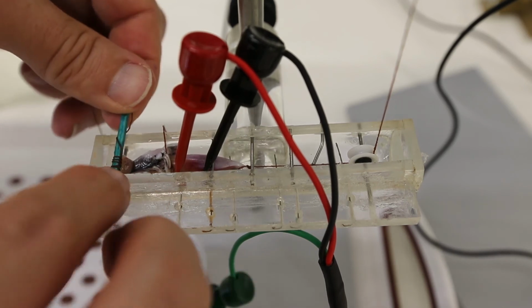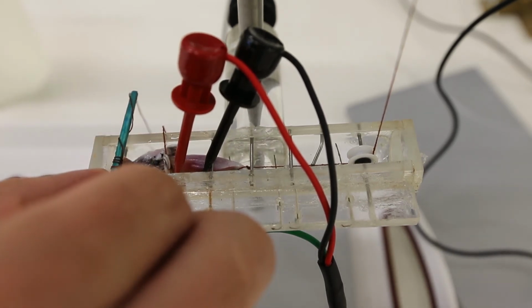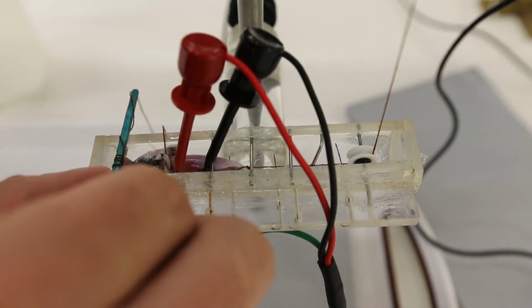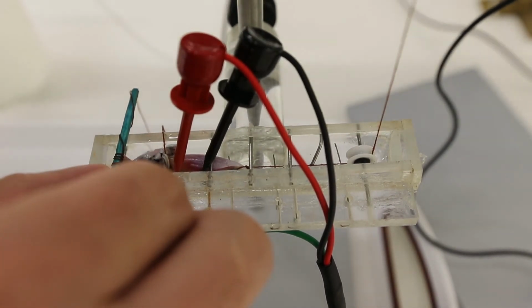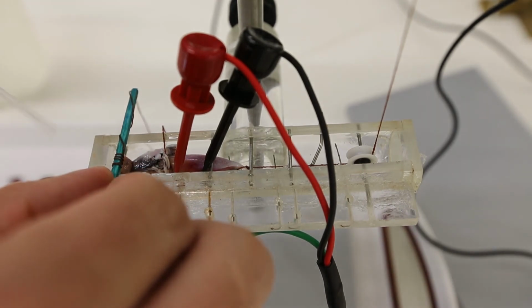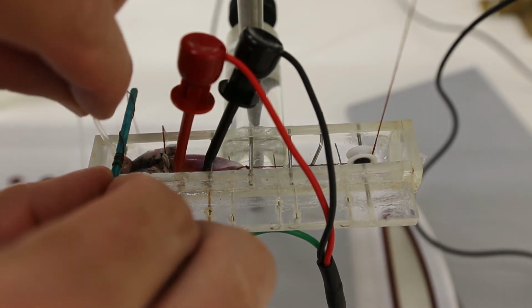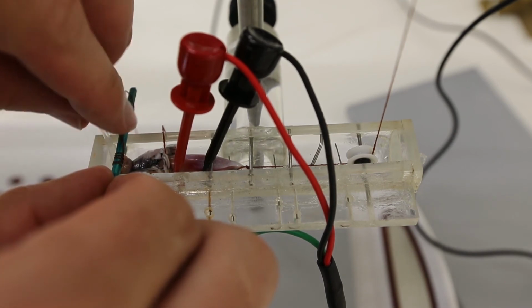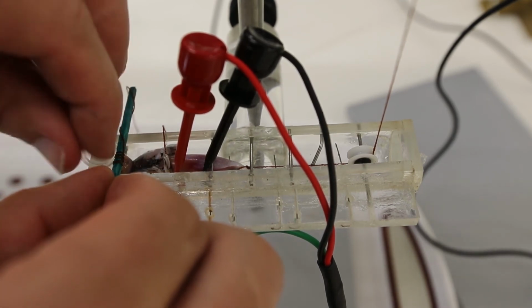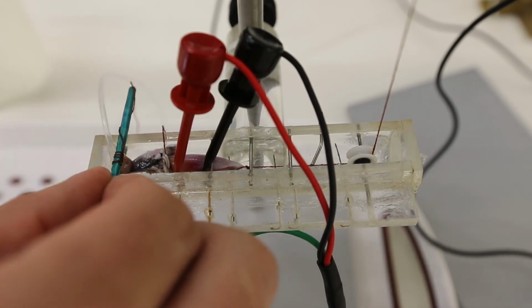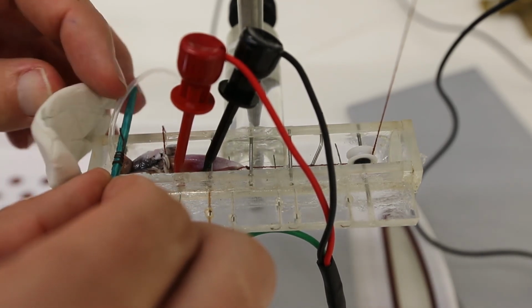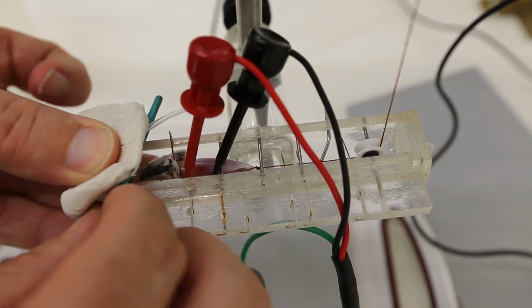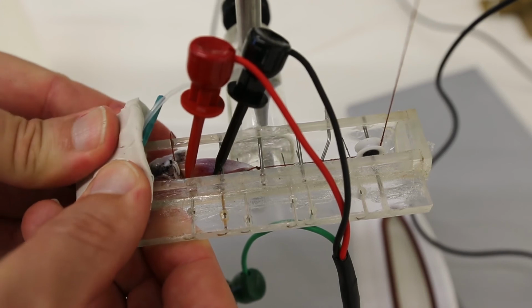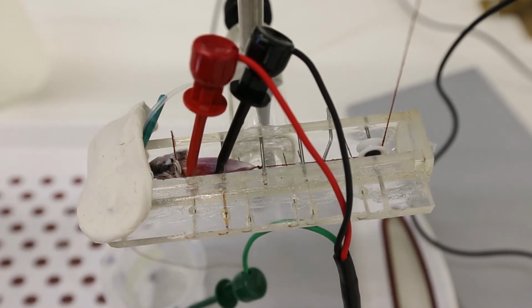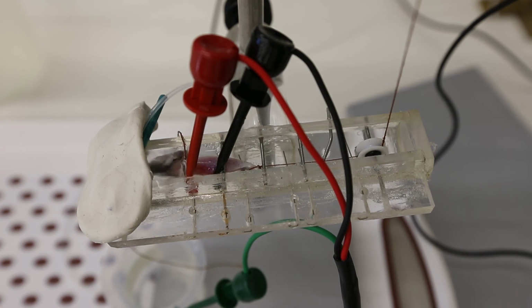You can also attach the oxygen tubing down the plasticine end of the tissue bath. To do this, remove the plasticine and slide the oxygen tubing underneath the match and the metal rod holding the muscle to the end of the bath. Make sure that the match hasn't become loose, then hold both the match and the oxygen tubing in place by replacing the plasticine. Then adjust the flow of oxygen to create a steady and gentle stream of bubbles.